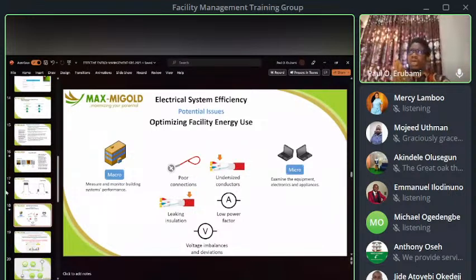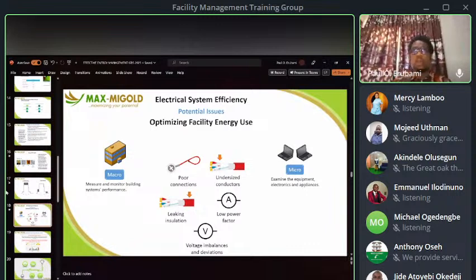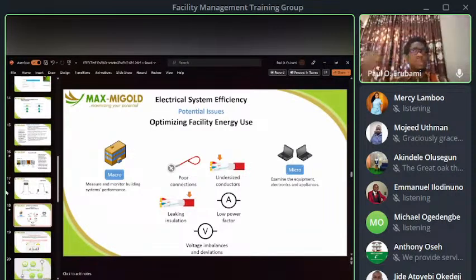So by the time you begin your investigations into each aspect, you'll see areas of energy consumption already deviating from their nameplate rating. For example, you have a pump rated to draw 3.14 kilowatts, but when metered, with all the noise and heating happening in it, you see 4.5 kilowatts in that reading. That's an indication you're losing 20-30% of the energy running through that pump, and you can immediately calculate all of those wastes.